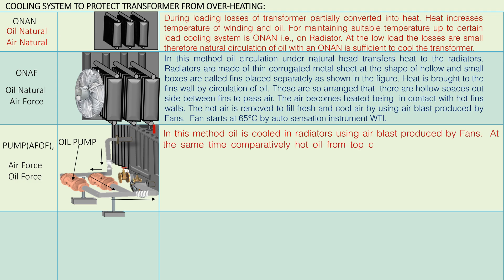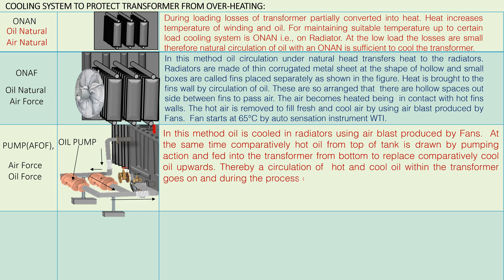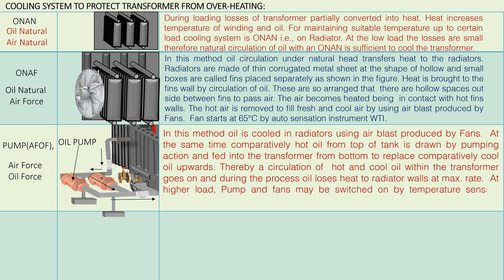In this method, oil is cooled in radiators using air blast produced by fans. Comparatively hot oil from the top of the tank is drawn by pumping action and fed into the transformer from the bottom to replace cooler oil, thereby circulating hot and cool oil within the transformer. During this process the oil loses heat to the radiator walls at maximum rate.